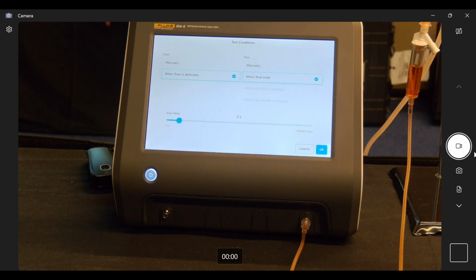Yes, in fact let me know when you're ready to do that and I'll get you a trade-in discount for your new IDA-6. So what will happen with the IDA-5, or any of these other analyzers on the market, is you're supposed to run a cleaning solution through it, something like Micro 90. The problem is if you don't get Micro 90 mixed exactly correct, or it sits too long, what happens? You get air bubbles.